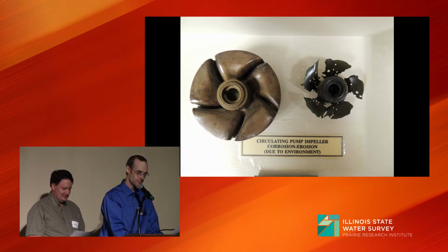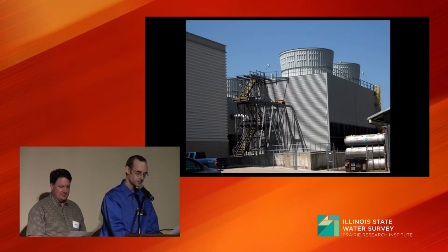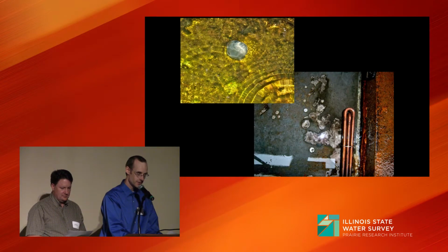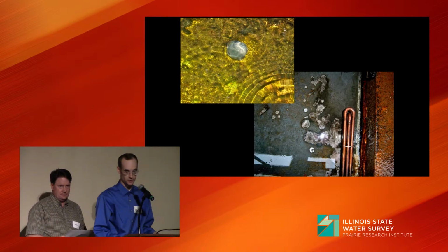Biological growth is also a major source of concern, especially in cooling tower systems, which remove heat from large buildings by evaporating water. These systems are an ideal breeding ground for all sorts of bugs. Here are some cooling towers on the U of I campus. Bacteria, algae, and fungi cause a number of serious problems in cooling and heating systems. Some bacteria eat iron, others excrete acid, which causes corrosion, while others exude a protective biofilm that greatly reduces heat transfer and efficiency.